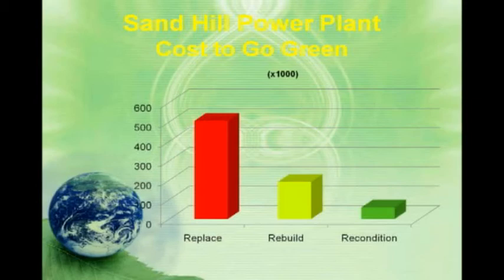That being said, we cannot dismiss, and we don't want to dismiss, the importance of an occasional replacement of a motor due to a very poor efficiency performance. And neither is Austin Energy. They're not dismissing the possibility that if they're running a motor that's operating at 70% efficiency, it's 40 years old, the reliability is in question anyway. Rather than rebuild that motor, I might consider dropping $100,000 on a replacement and getting some return very rapidly. On motors that are drawing that much power with that much of an efficiency difference, that's huge. That wasn't the case in these situations.